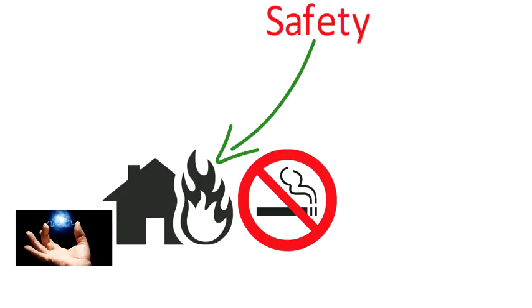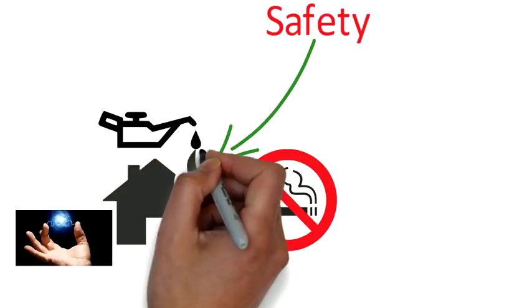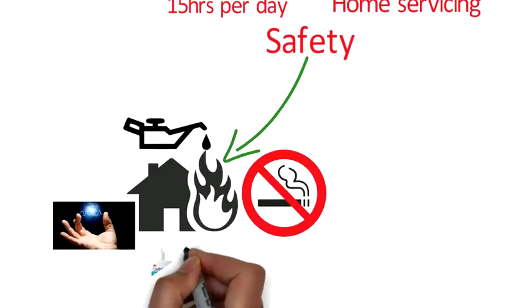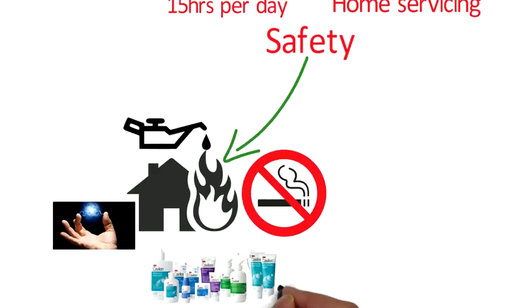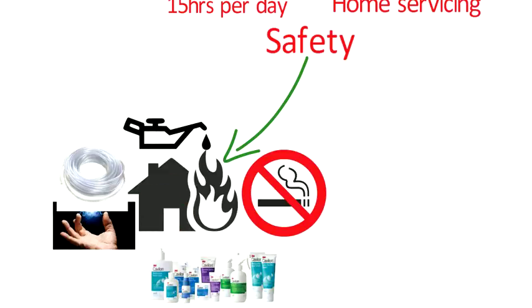So no smoking. Oil, grease or petroleum products mustn't be used near or on oxygen cylinders or concentrators. Patients shouldn't be using vapor rub or petroleum jelly, excessive amounts of skin lotion or face cream, aerosol sprays whilst they're receiving oxygen. They shouldn't be using oxygen close to any source of ignition or heat. Once they have finished whatever therapy they are receiving, they should turn off the flow of oxygen.